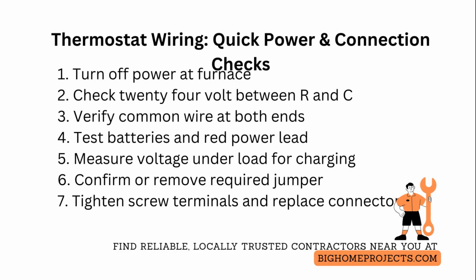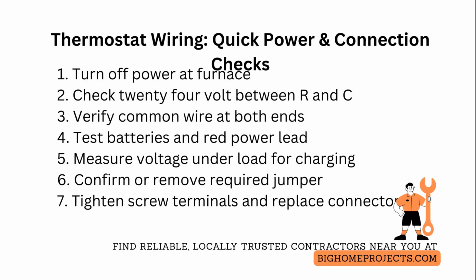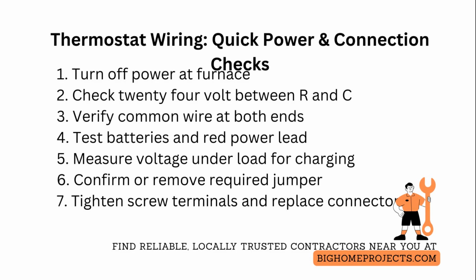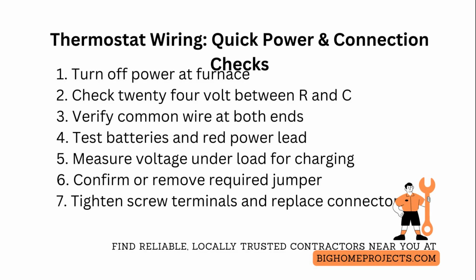Confirm the common wire is actually connected at both the thermostat and the control board. Loose commons are the most sneaky cause of intermittent power. Use needle nose pliers and a magnifier to inspect for frayed strands touching other terminals.